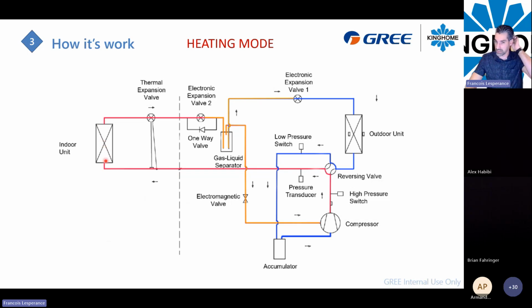So the same process, but inside of it now it's hot refrigerant. So inside your house, you will have warm temperature going out. And then the thermal expansion valve is equipped with an internal bypass, so this is not acting like a metering device in that case. That thermal expansion valve is not in use in heating mode. The refrigerant will flow through without restriction.